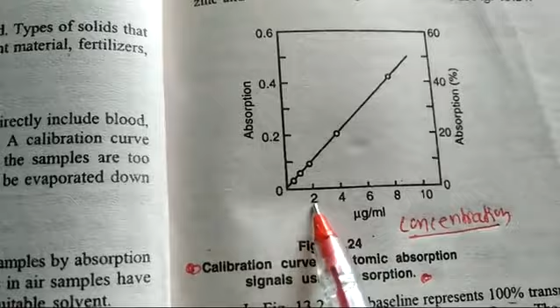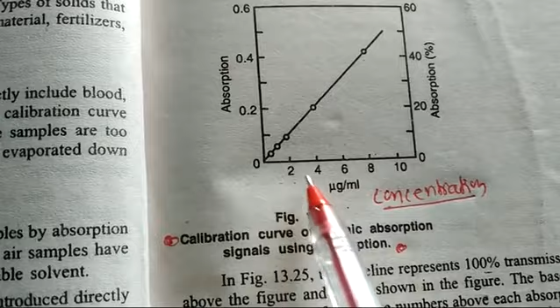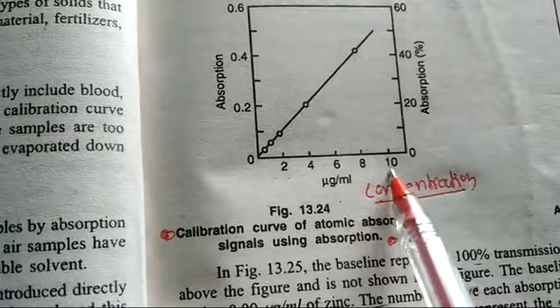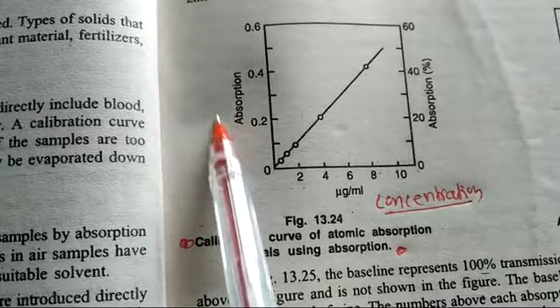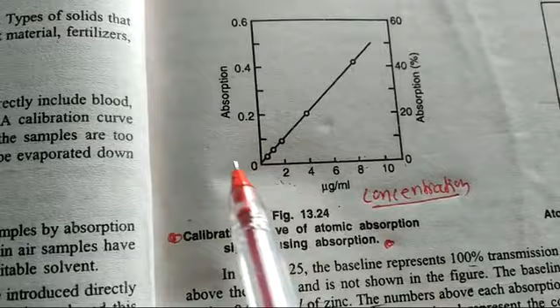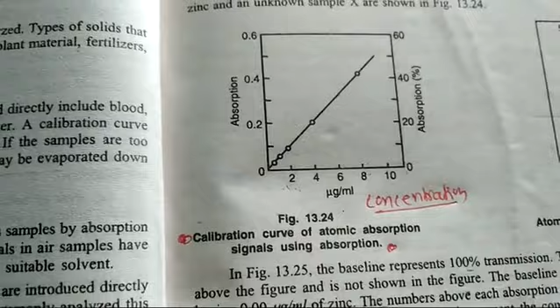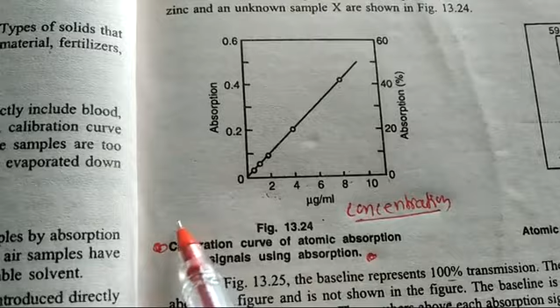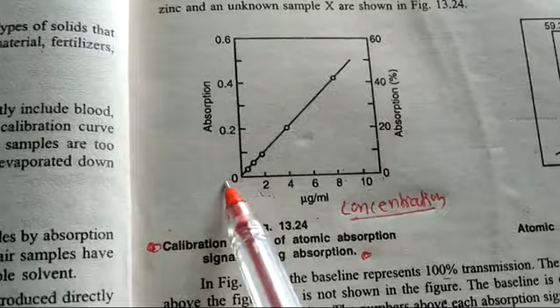In this calibration curve, we make known concentrations. Suppose we detect nickel metal atoms from an unknown sample. So first we prepare known concentrations: 2 microgram per ml, 4, 6, 8, and 10 microgram per ml. And we measure the absorbance against this concentration. Firstly, in the instrument we will measure the blank. In the blank there is no absorbance, zero absorbance or 100% transmittance.